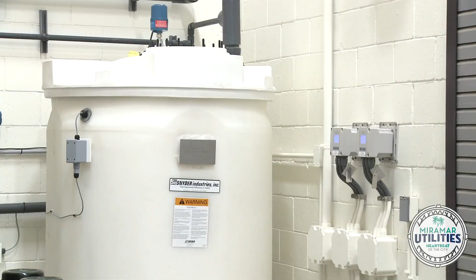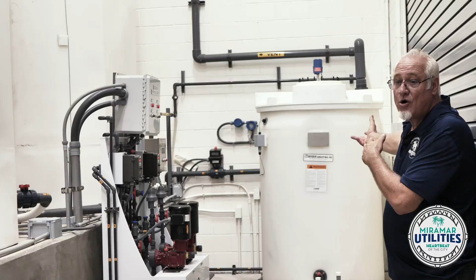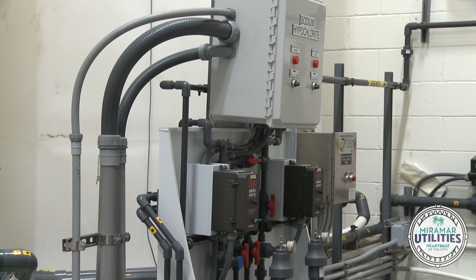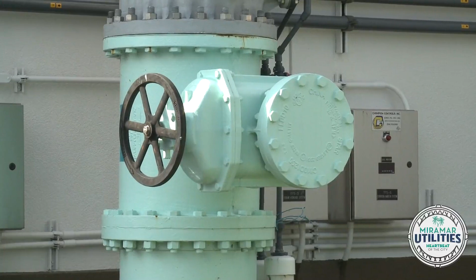We use a day tank here, so we only use 1 day's worth of chlorine at a time. We feed this chemical through metering pumps over here with the black and red pumps, and they speed up and slow down with the flow of the water to make sure it's an exact feed rate all the time. We also have an online monitoring system that monitors the chlorine residual so we can run these pumps accurately. Back out in the sunshine, the aqua pipe tells us that the water has been treated and is almost ready for its final stages of processing.